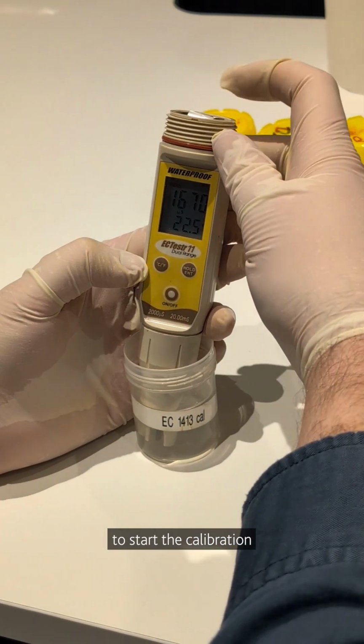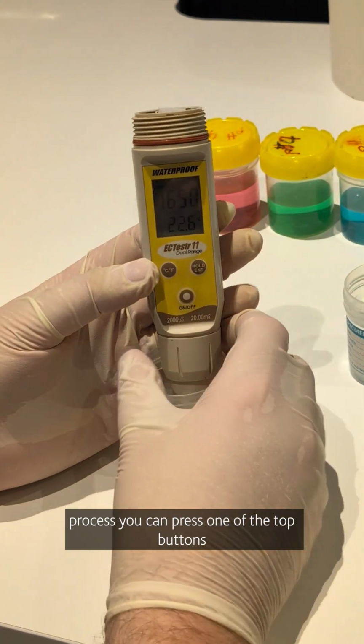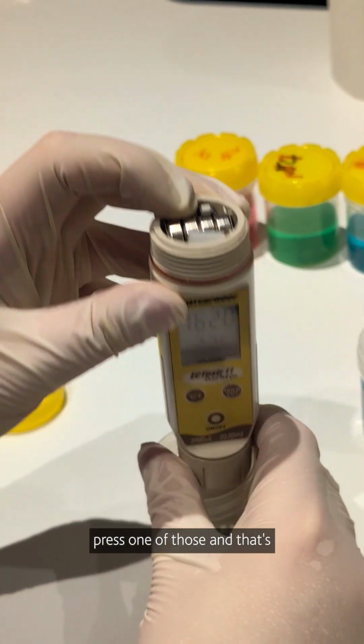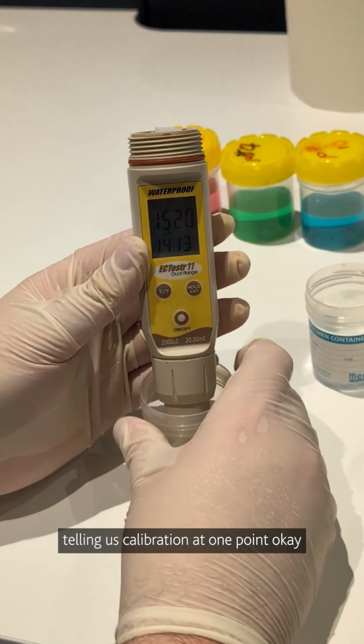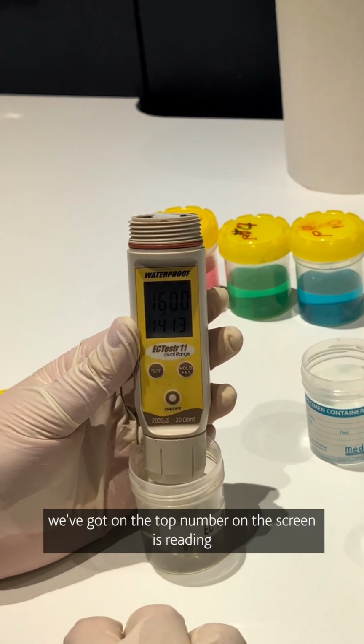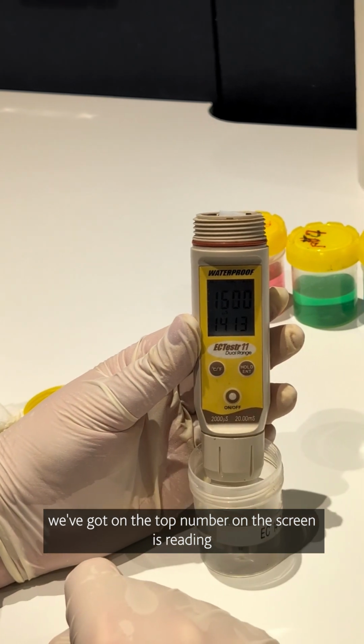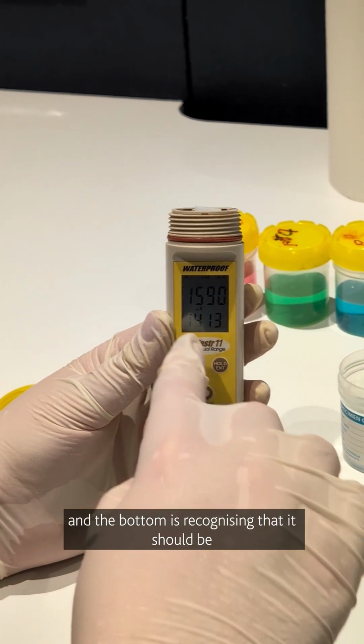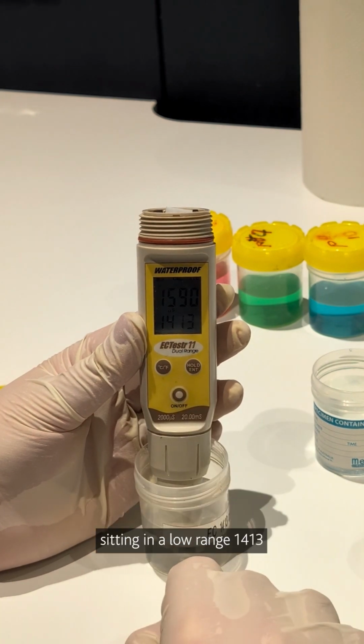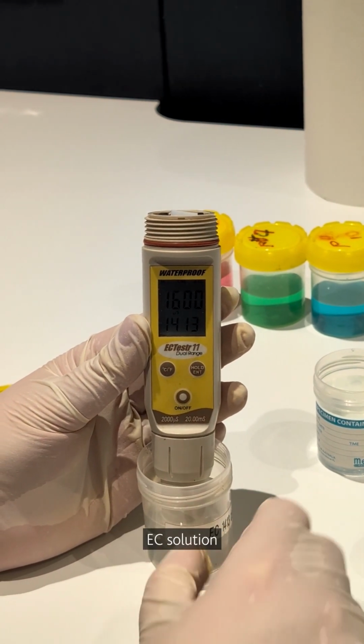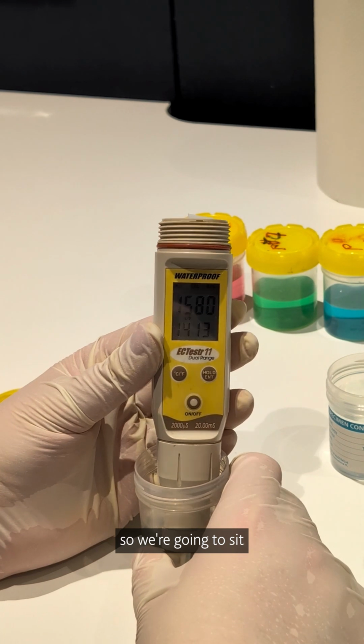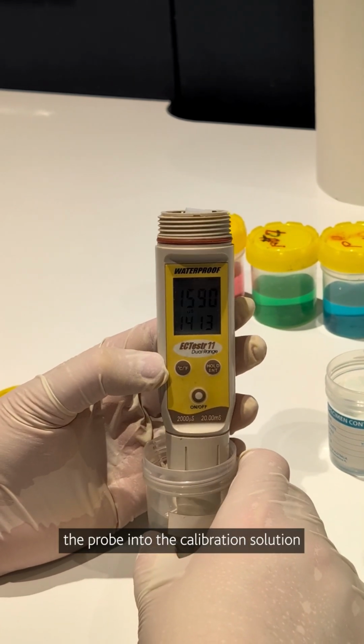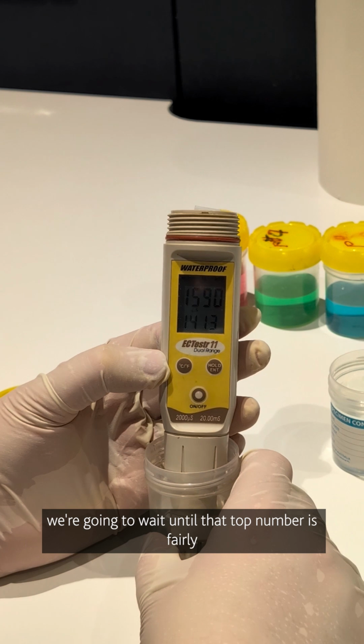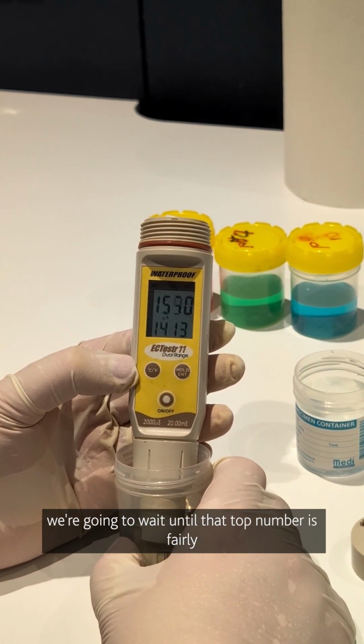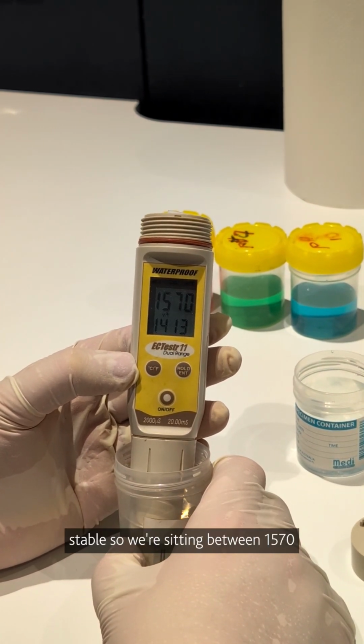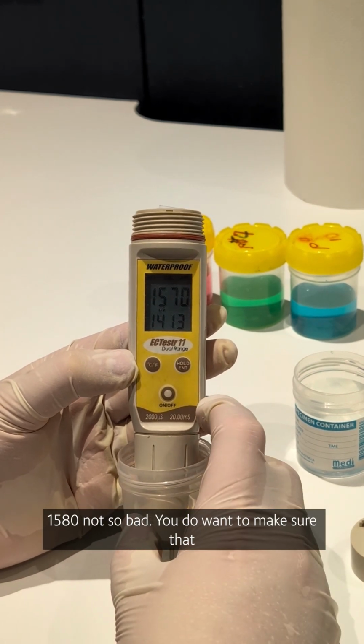To start the calibration process, you can press one of the top buttons. So one of the top buttons that are up here, press one of those, and it's telling us calibration 1 point. Okay, so now the top number on the screen is reading what the meter is reading, and the bottom is recognizing that it should be sitting in a low range 1413 EC solution. So we're going to sit the probe into the calibration solution, give it a little bit of a swish. We're going to wait until that top number is fairly stable. So we're sitting between 1570, 1580, not so bad.